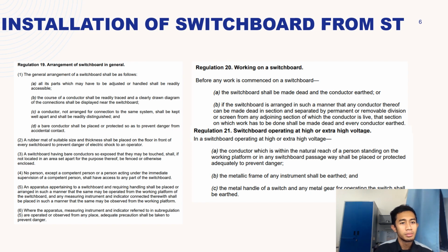Regulation 19, arrangement of switchboards in general. A rubber mat of suitable size and thickness shall be placed on the floor in front of every switchboard to prevent danger of electric shock to an operator. A switchboard having bare conductors so exposed that they may be touched shall, if not located in an area set apart for the purpose thereof, be fenced or otherwise enclosed.